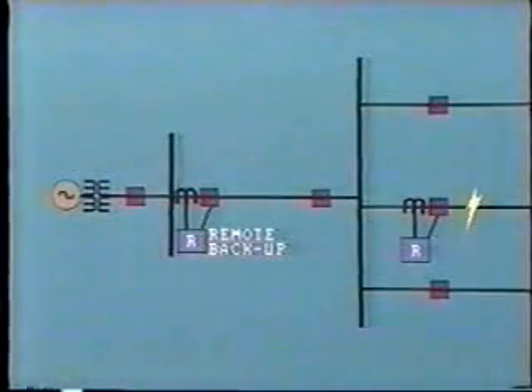Backup protection is important so that if the primary protection fails to clear the fault, the backup will take over and operate after a short time delay. In all situations, the objective is to provide protection which is sensitive, selective, and reliable. We'll be looking at the various line protection schemes as we proceed through this tape.